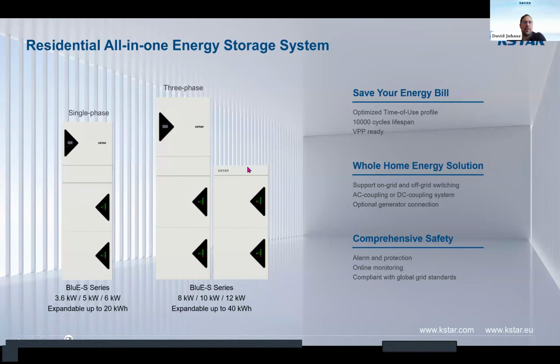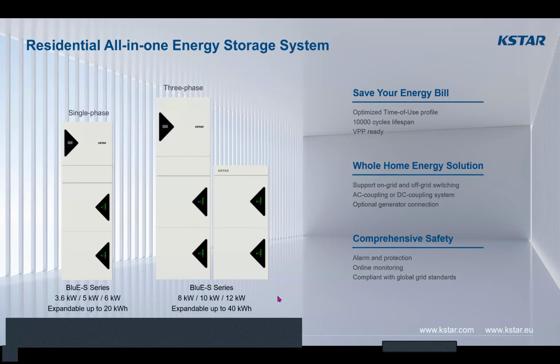It depends on the inverter. How many inverters are you using? Because the maximum power that can go out from one inverter is the nominal power of the inverter. So if you are using 40 kilowatt hours of storage capacity, to achieve the 0.5 C you need at least two pieces of 10 kilowatt inverter.